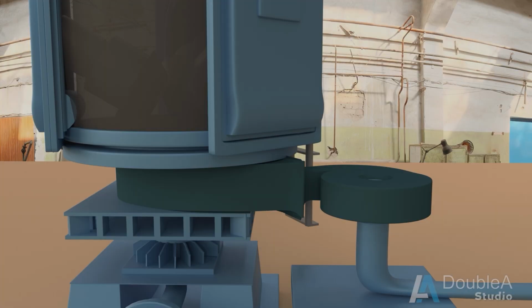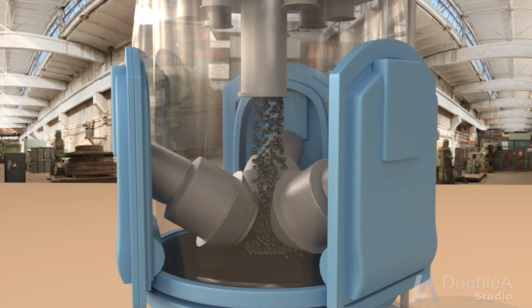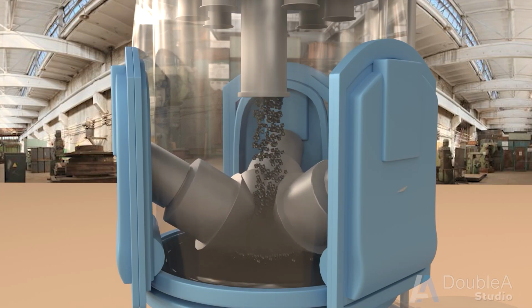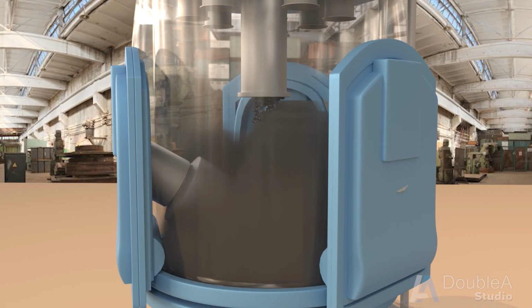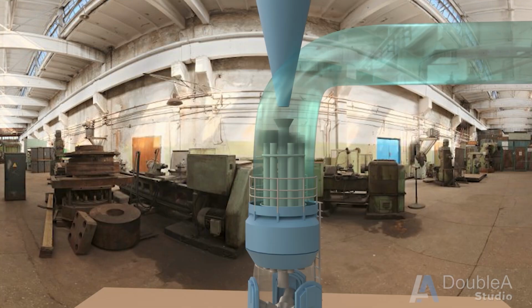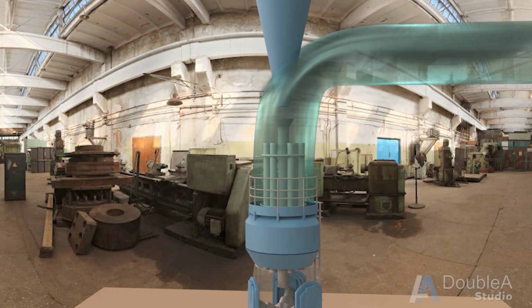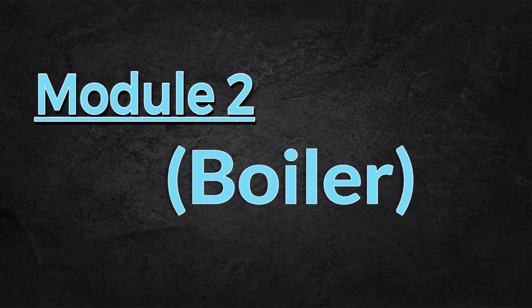Gearbox and drive rotate the bowl of the mill. Crushed coal enters through the coal feed pipe and falls on the rotating bowl. The rotation imparts centripetal force on coal particles and forces them to the outer periphery to press coal between the grinding rolls and bowl.